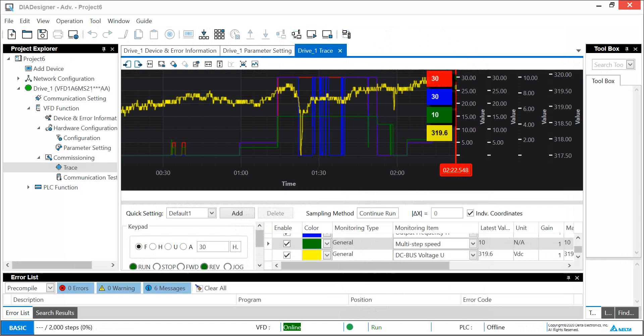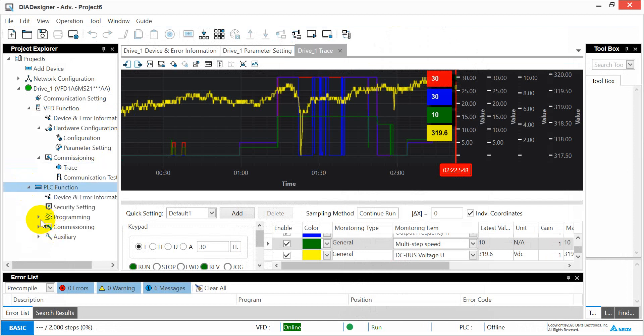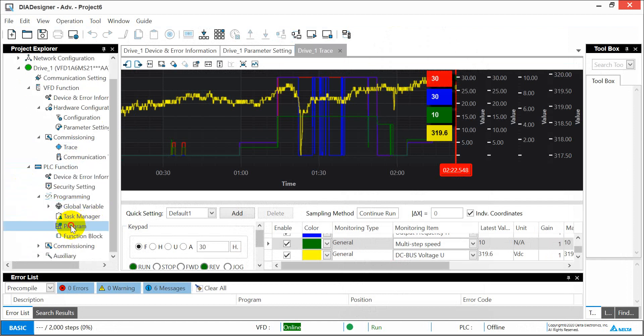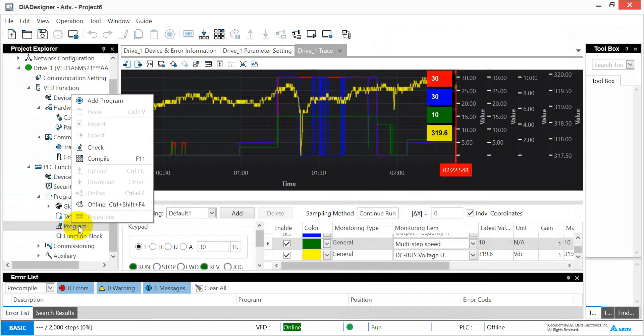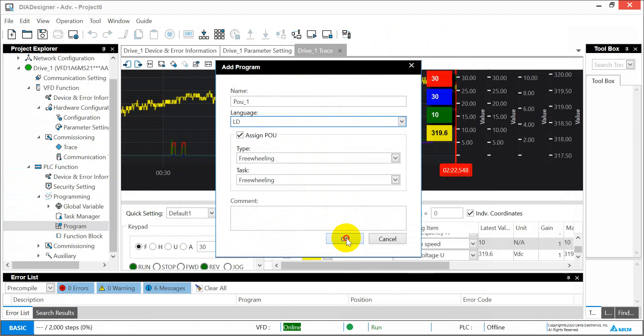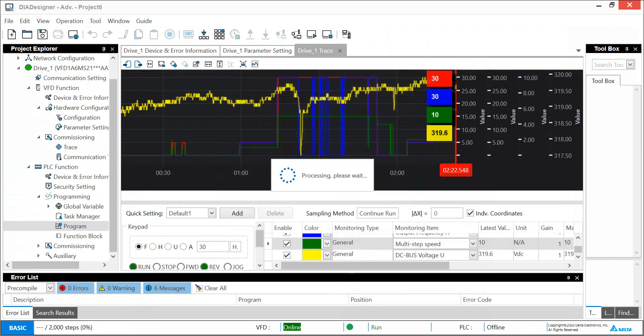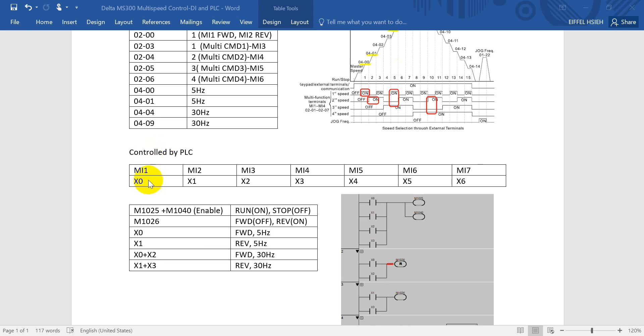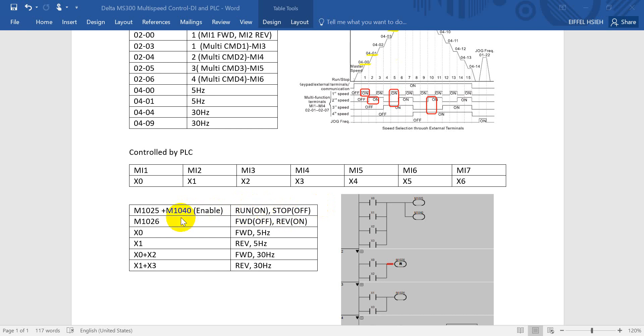We can go back to the software and then add down the program. Here we can add the new program. Because here we support only ladder, we click this one. For the PLC control, as I mentioned at the beginning, we will use only 4 digital inputs. Here is the relevant devices that we will use in the program. First one is special register M1025 and M1040. This one is to control inverter run and stop. This one basically controlled by M1025, but once we want to use this function we have to enable M1040.